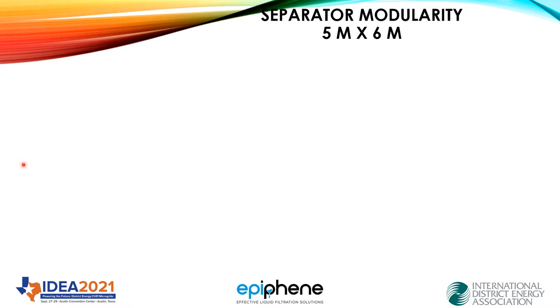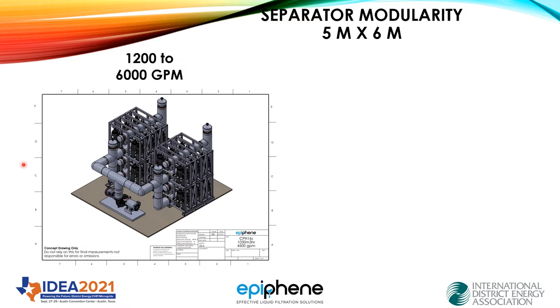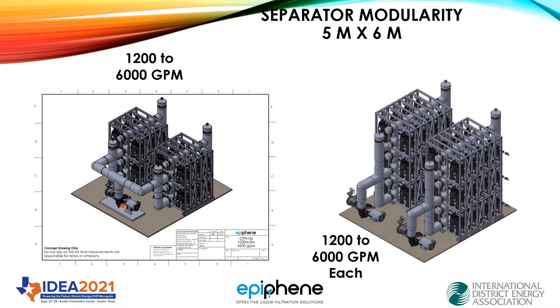Not only did we have requirements where we could go horizontally in our expansion, but we can also go vertically. We were challenged to provide a very high flow in a five-meter by six-meter space. Here's our first option: 1,200 to 6,000 gallons per minute, where each side is half of that — so 600 to 3,000 on each side fed by a single pump, centrifugal or split case. Then they asked us to increase the flow rate, so we went up another level — each one of these can handle 6,000 gallons a minute apiece for a total of 12,000 gallons a minute.